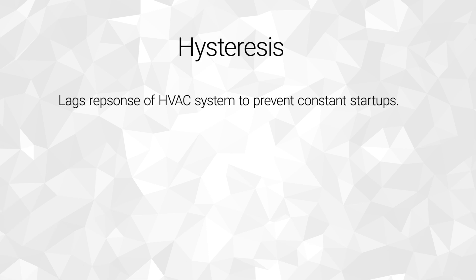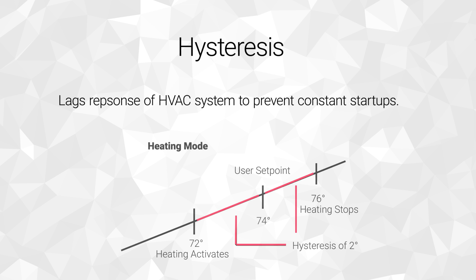Hysteresis is a way to lag the response of your HVAC system for the purposes of saving energy and equipment wear and tear. For example, with the set point at 74 degrees in the winter, the system may warm the space to 76 degrees, shut off, then allow the space to cool down to 72 degrees before heating again. Typically on newer thermostats, the hysteresis and dead bands are pre-programmed into the controls, so there's no need for occupants to worry about these features. Overall, the minimalism of a single set point makes for simple, intuitive user interaction.